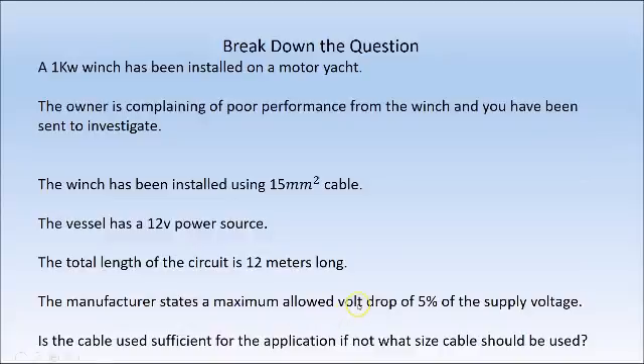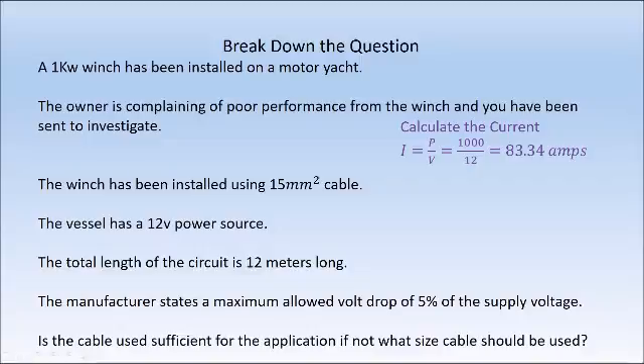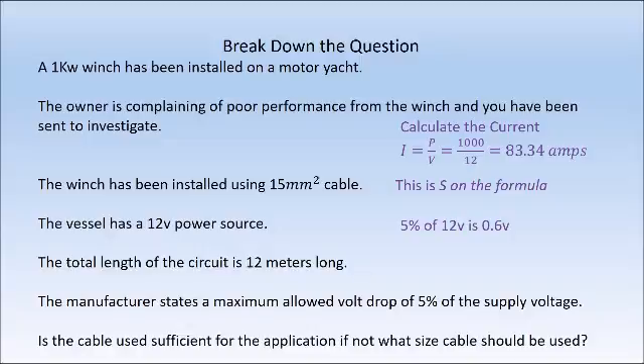We need to break down our question and find the data we need. We need to calculate our current — same as previously, power divided by volts equals current. 1,000 divided by 12 gives us a current draw of 83.34 amps. This time we want to find the volt drop, so we need to input the cable size — in this installation we'll use S in the formula, which is our cable size, so we input 15 millimeters squared. The vessel has a 12-volt power source, the circuit is 12 meters long — and as it says total length, you don't need to double it. The manufacturer states a maximum allowed volt drop of 5%, so 5% of 12 volts is 0.6 volts.